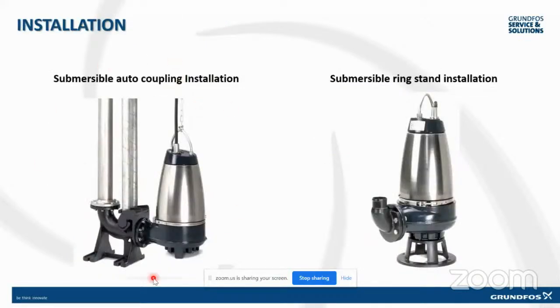This is the installation. Ye installation basically submersible installation hai, jismein hum ek guide rail ki help se we put the pump down, aur yahan pe ye connection hota hai, jisse bina fixed connection ke you can have a connection which is flexible. But it has an arrangement to ensure that when the pump is running, there is no leakage here, because the sealing arrangements are done in such a way that when the pump is running there is no leakage happening at that point of time. And if you have to take the pump out, nobody needs to go into the pit. You can just lift it from the chain and take the pump out. So this is an auto coupling kind of installation.